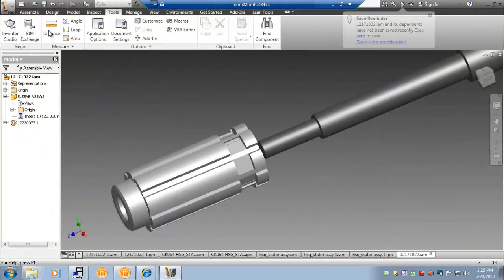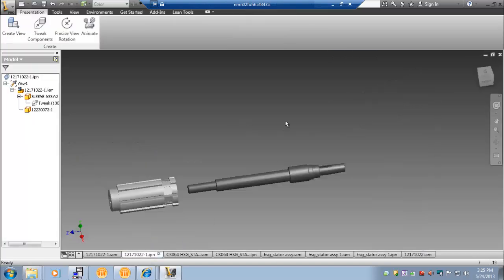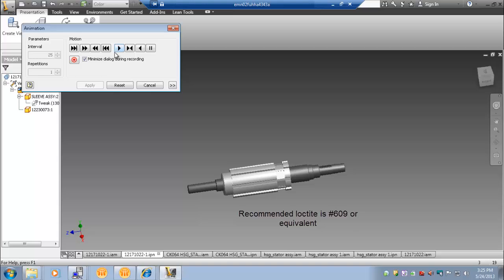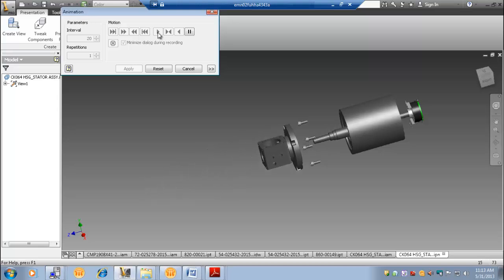For this assembly, we will be Loctiting the rotor to the shaft. The shaft outer diameter is 14mm with a G6 tolerance. Our CK064 rotor has an inner diameter of 14mm and will be slip fitted onto the shaft — the tolerance to support this is H7. The shaft has a step on it, similar to the step put into the housing, which will ensure that the rotor is centered under the stator lamination. The recommended Loctite is number 609 or equivalent. You can now see how the entire assembly goes together. The shaft of the motor extends beyond the rear housing for a clamp-on encoder, and at the output the shaft extends past the flange to engage the pulley.